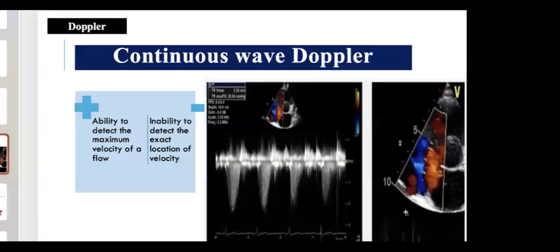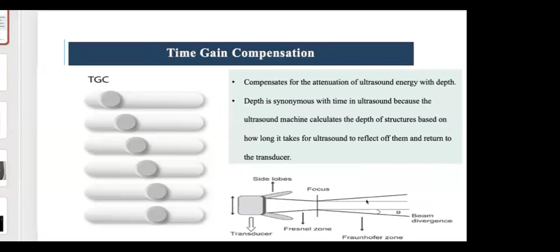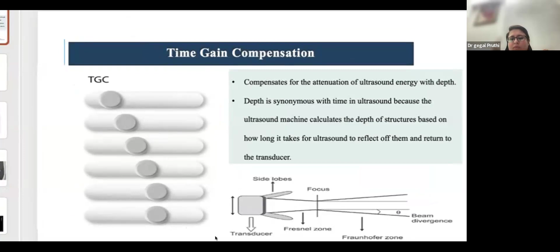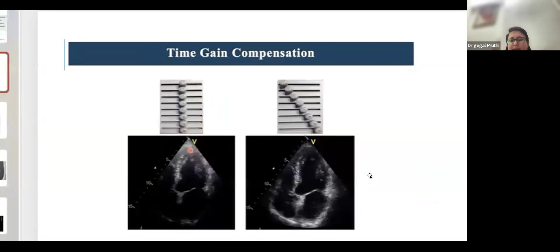The next question is about gain. It has been already discussed when to use time gain and lateral gain compensation. I think Dr. Gegal can just repeat on that. So time gain compensation you can use for the far field structures. You can use the step ladder pattern or choose the area of interest and adjust your time gain compensation accordingly, mainly for the vertical things for the far field zone. Whereas the lateral gain compensation, you can selectively amplify across the width of the image display. It is mainly for your endocardial borders. It is mainly for visualizing the lateral walls.